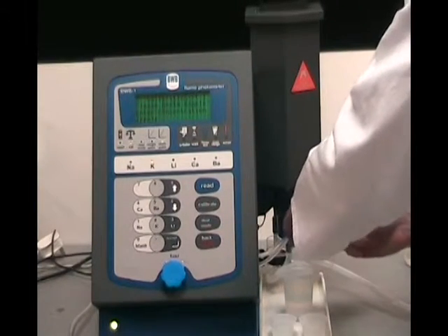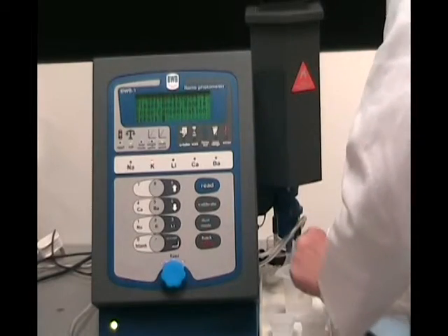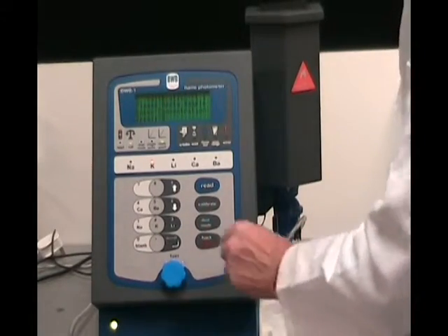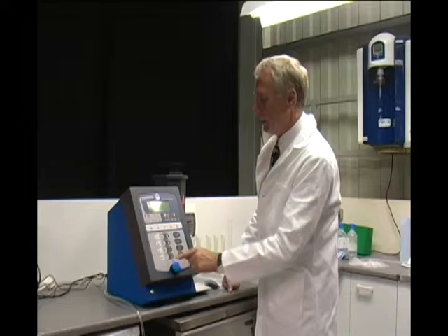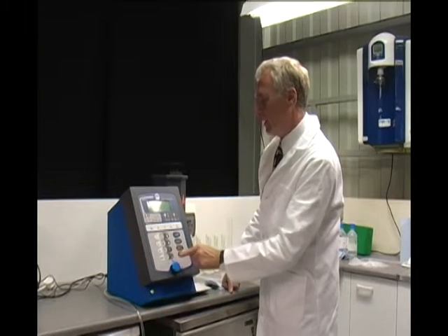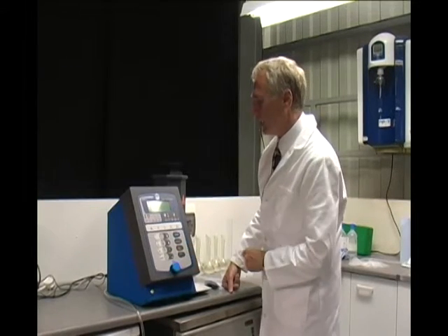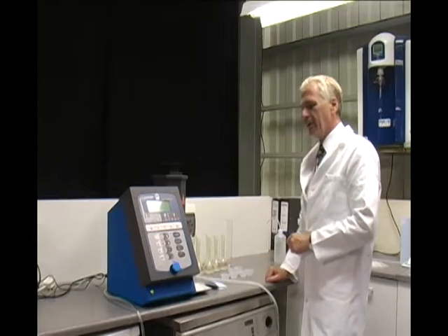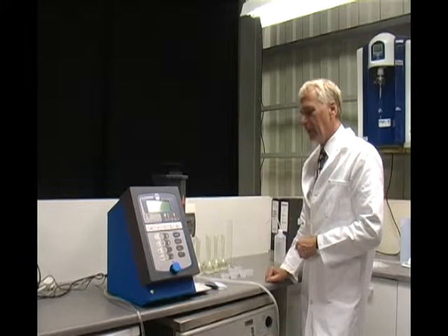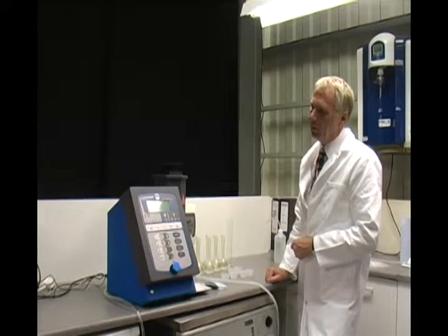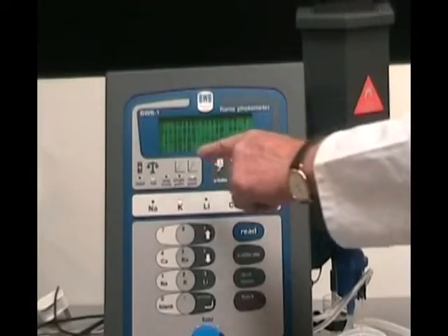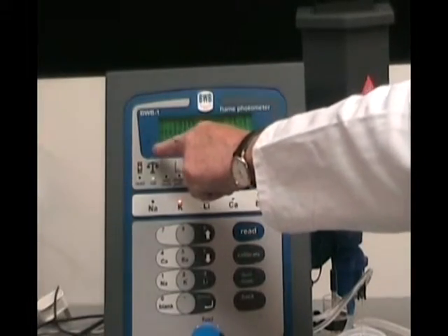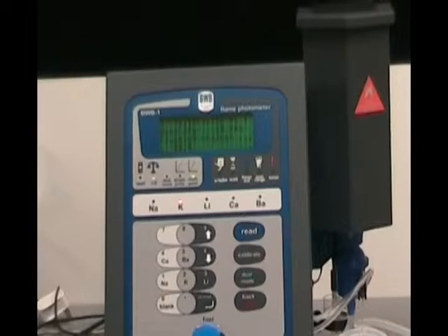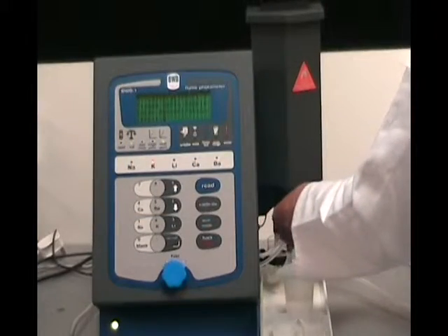That has now determined that the system is stable and is taking the reading for the blank. Wipe the tube, taking it out of the blank and put it into my first sample. This is going to be 10 ppm of potassium. Press accept and press accept to start the process. Once again it's flushing the chamber. We've got a graph on the left hand side which shows us the signal is rising and is now going to a flat level. That has now taken the reading for 10 ppm.